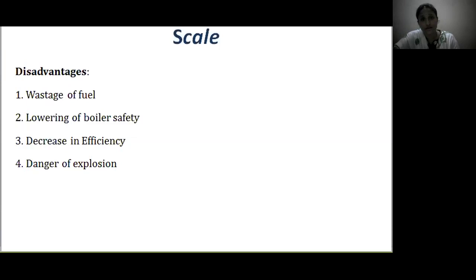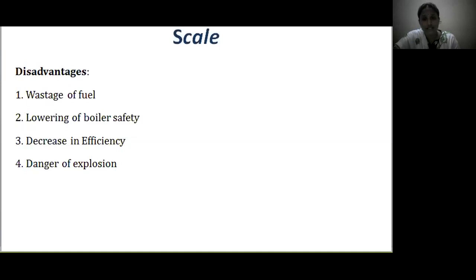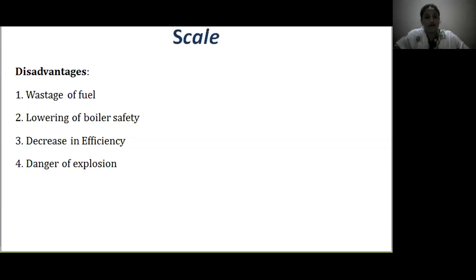What are the disadvantages of scale? Obviously, it wastes fuel consumption — as the thickness of the scale increases, fuel consumption also increases. It also lowers boiler safety: due to overheating, the material becomes soft and thin, decreasing safety. Scales in tubes and pipes cause choking and decrease boiler efficiency. There is also a danger of explosion: due to scale formation, uneven temperature distribution leads to cracks in the scales, water in the cracks gets more heated and develops more steam, and a sudden increase in steam pressure leads to explosion of the boiler.